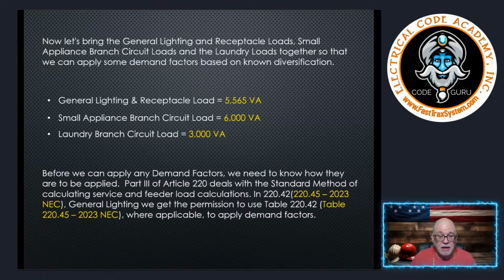Now, again, if it's a multifamily building that has a laundry facility on site, then you have some allowances to be able to not put the laundry receptacle in because it's available to all the tenants or all the people that are at the complex, and there's a separate laundry facility. Then that's different. Then you don't have to install the receptacle at all, but you're required to have the laundry circuit. And in a single family dwelling, you're required to install the laundry receptacle outlet. Okay? And I believe that is in 220.52(D), if I'm not mistaken.